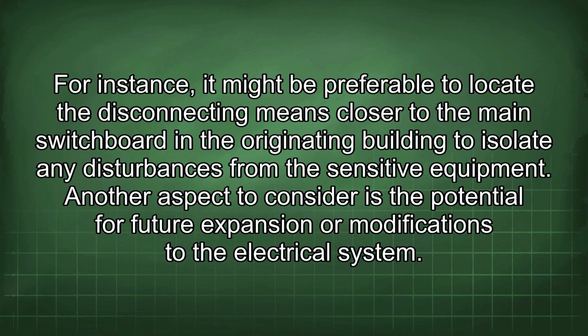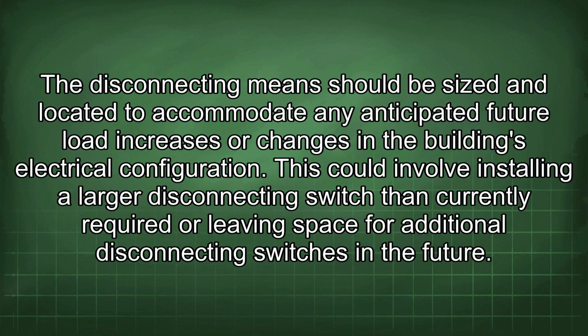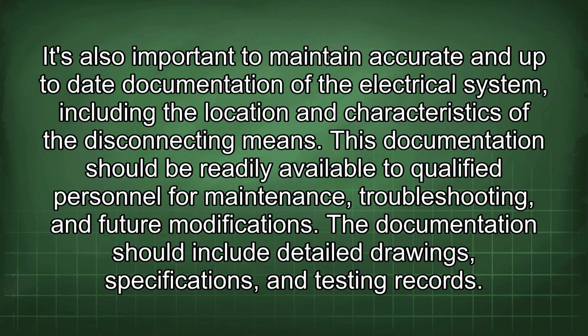Another aspect to consider is the potential for future expansion or modifications to the electrical system. The disconnecting means should be sized and located to accommodate any anticipated future load increases or changes in the building's electrical configuration. This could involve installing a larger disconnecting switch than currently required or leaving space for additional disconnecting switches in the future. It's also important to maintain accurate and up-to-date documentation of the electrical system, including the location and characteristics of the disconnecting means. This documentation should be readily available to qualified personnel for maintenance, troubleshooting, and future modifications. The documentation should include detailed drawings, specifications, and testing records.